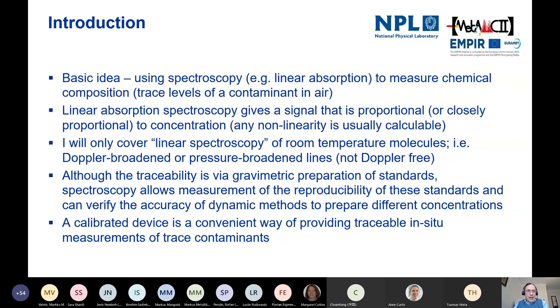I should emphasize that traceability for these measurements is really via the gravimetric preparation of standards, which the NPL gas metrology group is expert in. But spectroscopy does allow us to measure the reproducibility of these standards and we can verify the accuracy of dynamic methods used to prepare different concentrations. So if we can calibrate our spectroscopic instrument, it's a very convenient way of providing traceable measurements in the field.